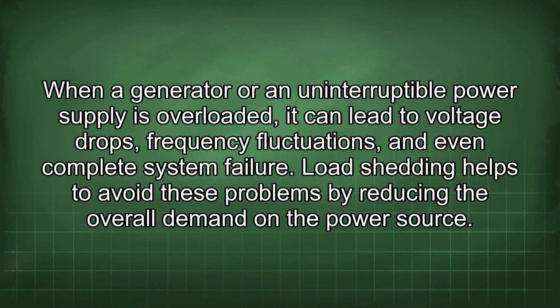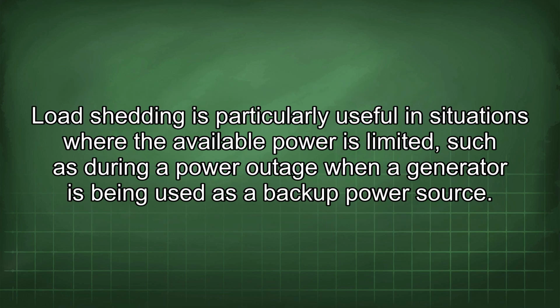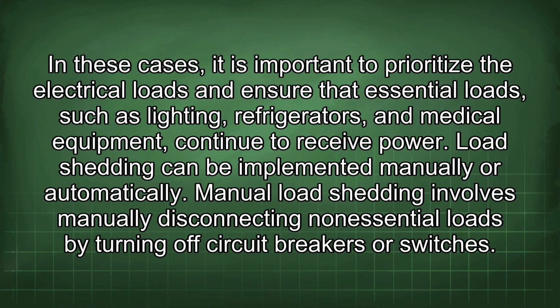When a generator or an uninterruptible power supply is overloaded, it can lead to voltage drops, frequency fluctuations, and even complete system failure. Load shedding helps to avoid these problems by reducing the overall demand on the power source. Load shedding is particularly useful in situations where the available power is limited, such as during a power outage when a generator is being used as a backup power source. In these cases, it is important to prioritize the electrical loads and ensure that essential loads such as lighting, refrigerators, and medical equipment continue to receive power.